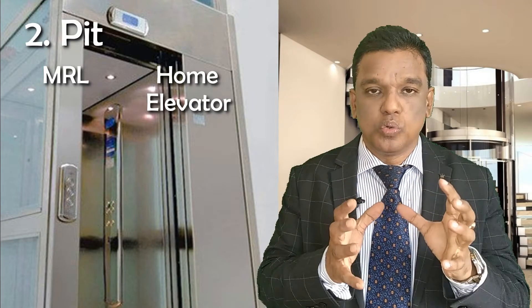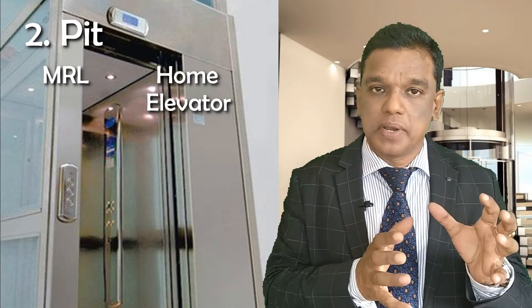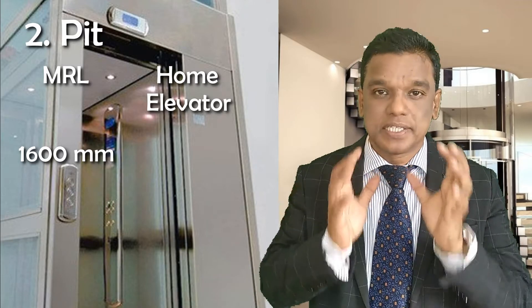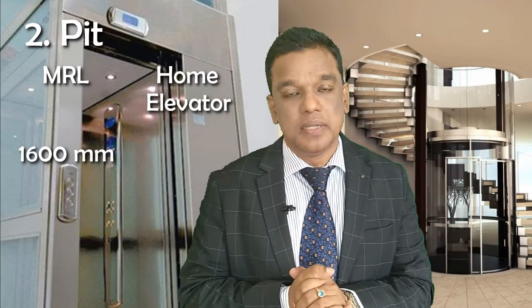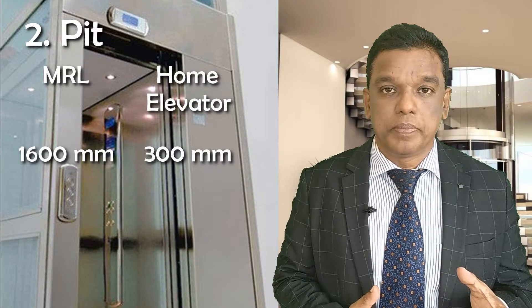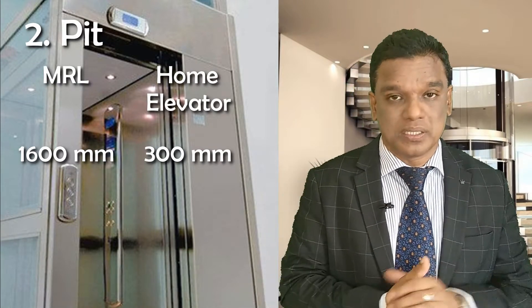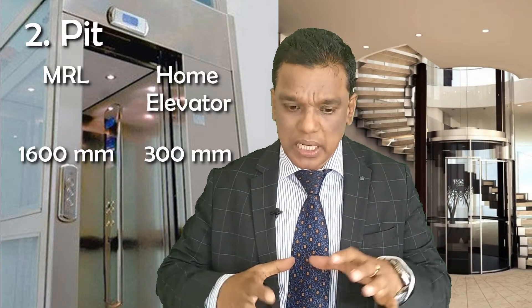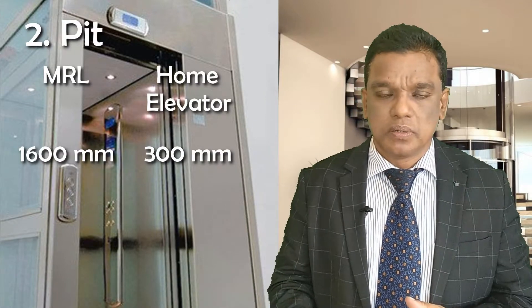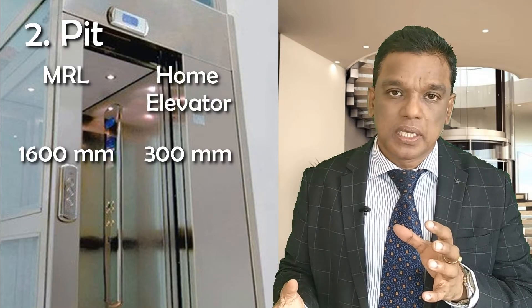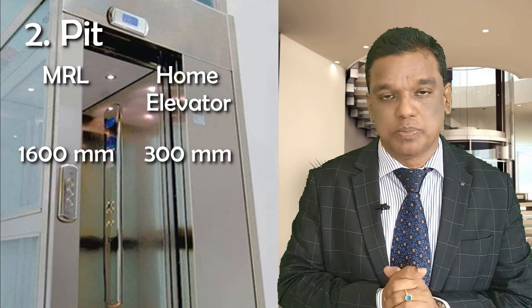Point number two: the pit depth in MRL — machine room less elevator — is 1600 mm, which is 1.6 meters. At the same time, in a home elevator the pit required is only 300 mm. The advantage of a home elevator is that where you cannot build a 1.6 meter pit, you only need to provide 300 mm. Even if there is no pit, you can raise the floor by 300 mm — about one foot. So the pit depth required is much less in a home elevator compared to 1.6 meters in MRL.